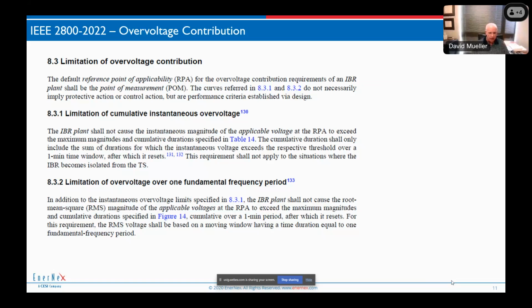So we're talking more about load rejection criteria and things like that, but you'll notice in 8.3.1, this requirement shall not apply to situations where we become isolated from the transmission system. So the interesting part about the main clause is the curves referred to do not necessarily imply protective action or control action. Okay, they don't imply that. And there's another sentence where it says we want the inverter manufacturer to design that in their equipment.